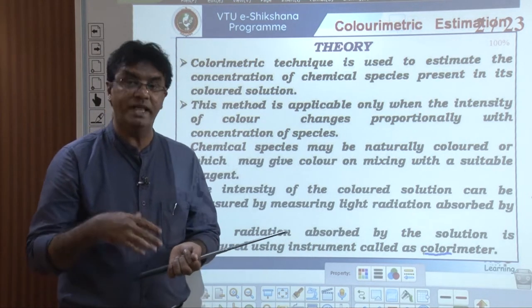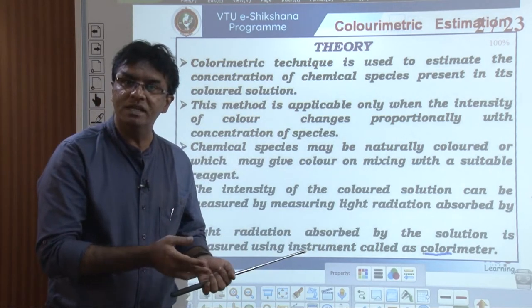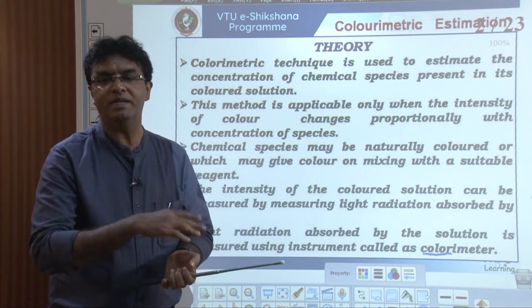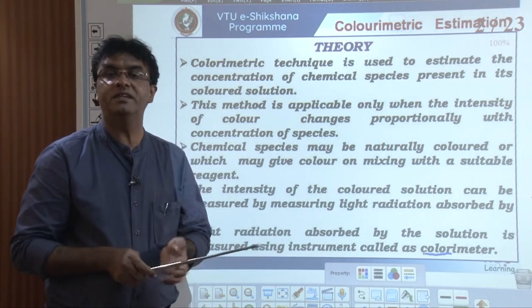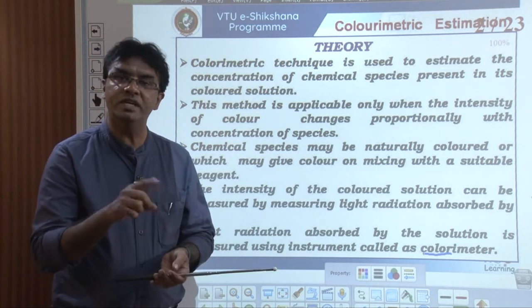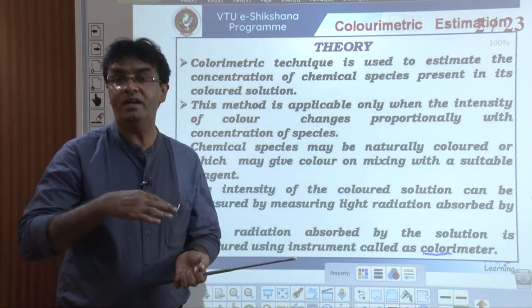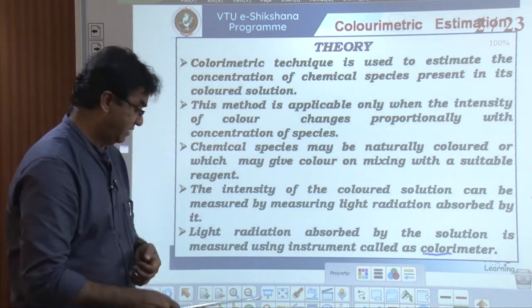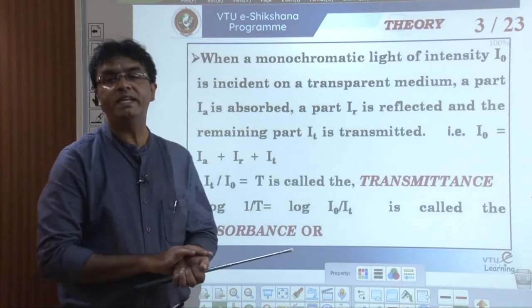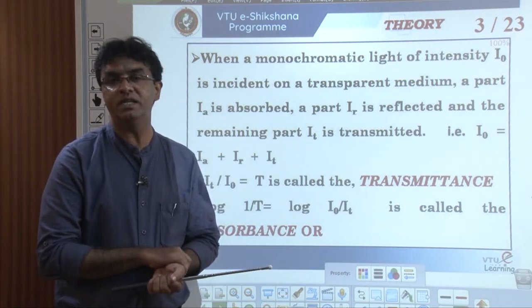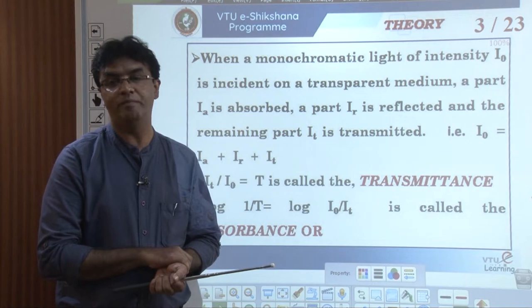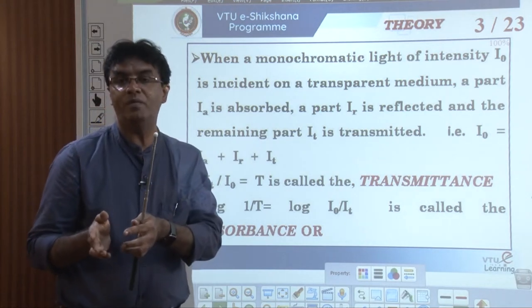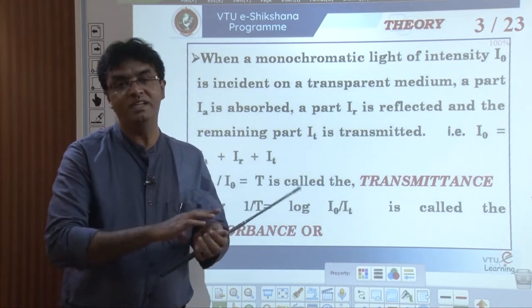There are some chemical species that may be naturally colored, and others that get color upon reacting with other chemical species. The intensity of the colored solution is measured by measuring the amount of light absorbed. We use the instrument called a colorimeter, and the entire concept — the amount of light absorbed by any colored solution — is governed by Beer-Lambert's law. Beer-Lambert's law talks about the relationship between the amount of light absorbed by any colored solution and the concentration of the solution.